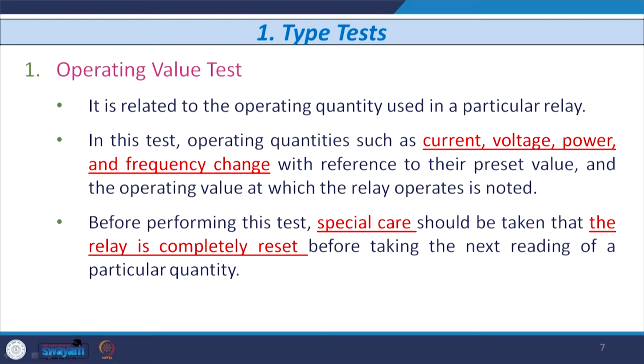This operating value test is related to the operating quantity used in a particular relay. If I use an over current relay, the operating quantity is current. If I use an over voltage or under voltage relay, the operating quantity is voltage. If I use a low forward power relay, the operating quantity is power. If I use a frequency relay, then the operating quantity is frequency. As I told you, the operating quantities, current, voltage, power, frequency, are considered with reference to the preset value.